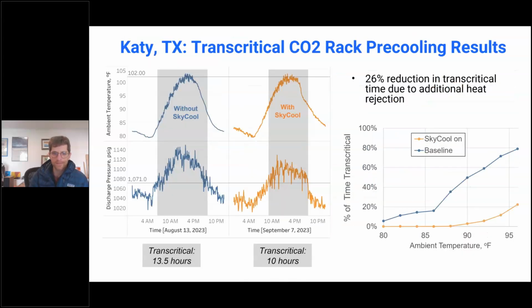And then in Katy, which is a much more humid environment, we're able to lower the amount of transcritical hours. So over the course of the summer, you can see here, at a given ambient, how much we were able to reduce the number of transcritical hours at a site. The curves on the left are, again, two similar days. You can see the lowering of the discharge pressure and associated power reduction, and fewer hours where it was transcritical for this particular day.